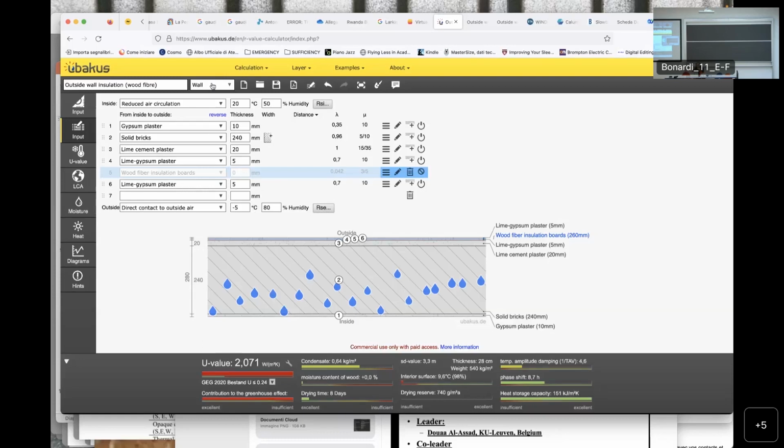So under these conditions, the software does simple calculations and shows you directly the result. Down here, it tells you the U value, which is quite high, and the fact that there is condensate. In this situation, as depicted by these drops of water here, the software tells you, wait a moment, water vapor will condense to liquid within the wall and in the long run will damage the wall, besides the fact that it changes its conductivity and makes it more conductive.